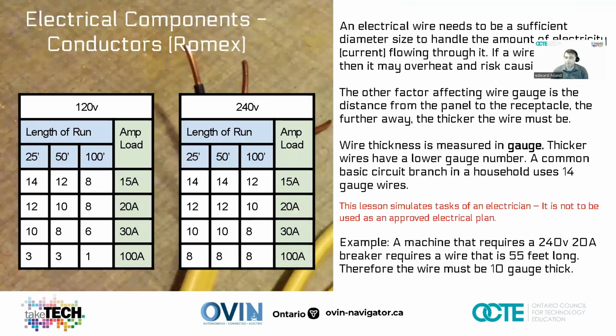I'd like to give an example. Maybe the most complicated part is discussing the thickness of wire that goes from the electrical panel to the receptacles—that's the gauge of the conductor. The gauge is the thickness; the lower the number, the thicker it actually is. Typically you have 14 gauge in your house, but if you have something like a dryer that takes more electricity, you'd go to a 12 gauge. If you look at the chart, it shows how far away it is from the panel and how much electricity is going to it, which determines the thickness of the wire.